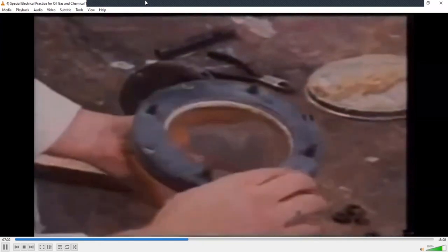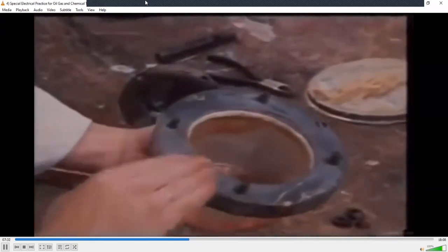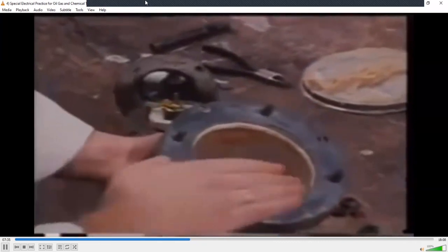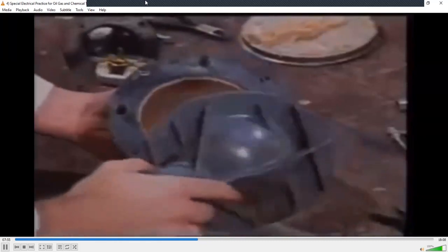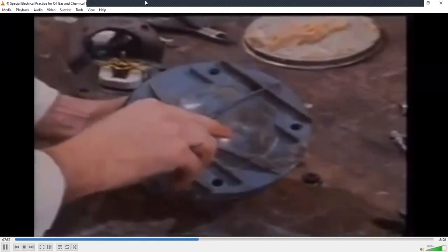It's important to remember that there is a great deal of difference between flame-proof and weatherproof fittings. Do not put a gasket between the flanges of a flame-proof fitting to make it weatherproof. This will invalidate its flame-proof certificate, as will any other modification of the original design. When reassembling these types of fittings, extra care must be taken to ensure that the flanges are clean.